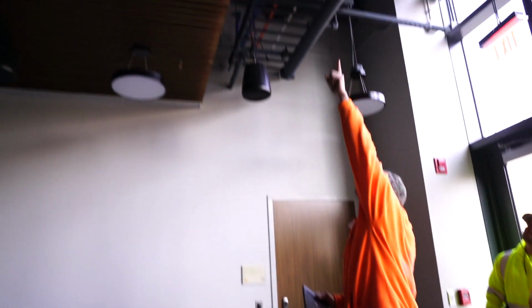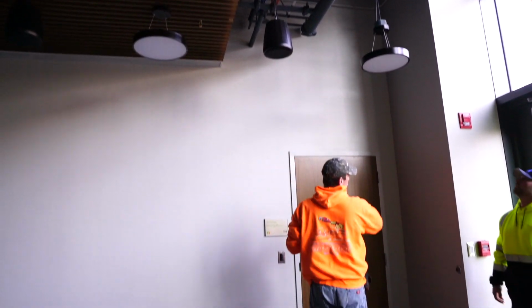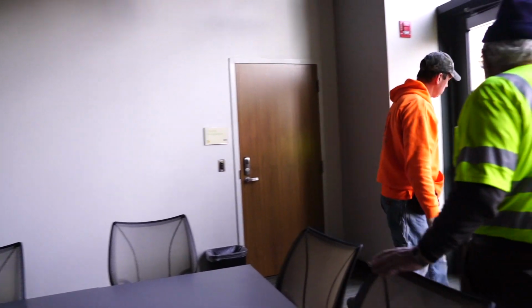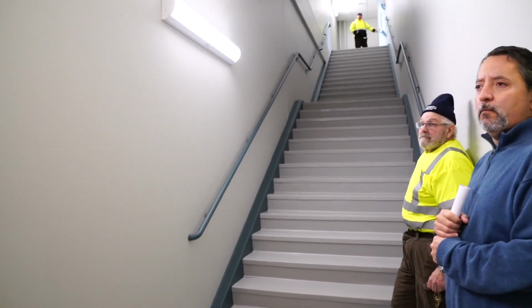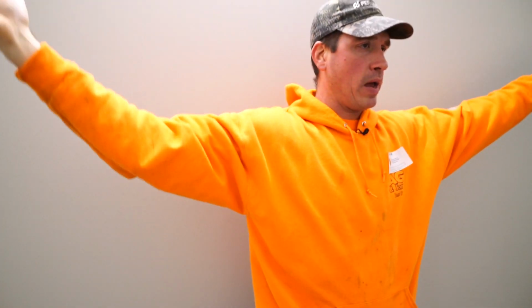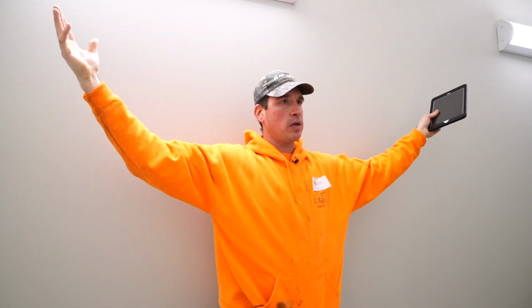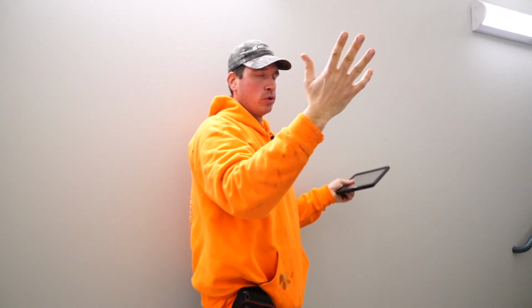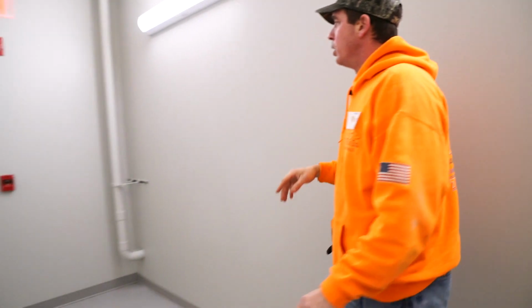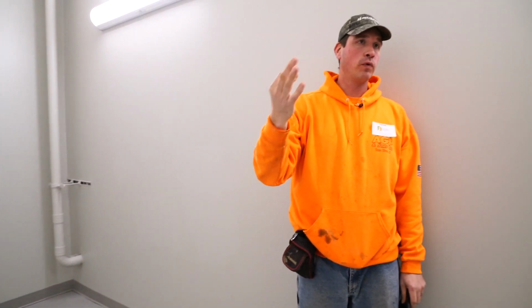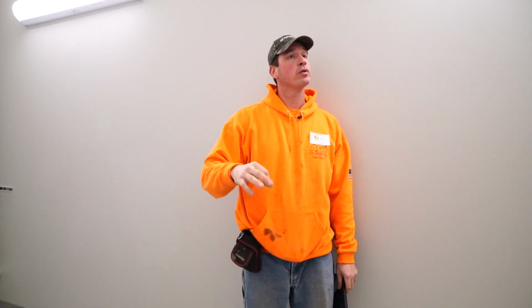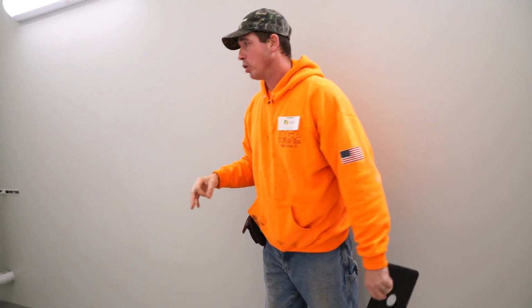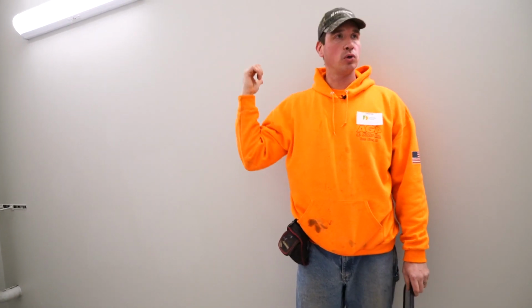We'll go upstairs. Okay. So you have this line that's coming up right here, going through. There's another hose bib right outside there. Yeah, right. Right, yep. And there's a valve inside that room, overhead. Okay. On either stairwell, that's a flat roof up top. You have 2 sets of roof drains on either end. So you have this one stairwell, either end has roof drains. That other far stairwell, there's roof drains on either end. The roof drains consist of a roof drain that ties in, goes to the underground, and then there's an overflow drain.